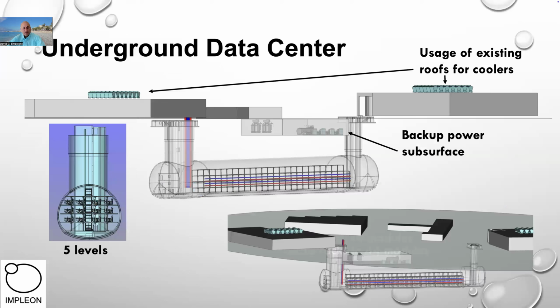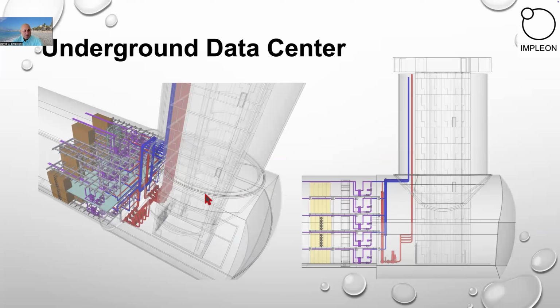And another thing is heat reuse. Usually a data center goes where the land cost is low and the energy cost is low. Afterwards, you start to think about heat reuse and realize that there is no one in the neighborhood, or you need to invest a lot of money in piping to be connected to the district heating grid. From that perspective, we created an underground data center, which allows us to bring 3,250 racks close to the users. We need just a shaft space of 10 by 10 meters, and we don't touch the above-ground buildings, and create this space underground. We have designed a row of racks with on-chip cooling, with door heat exchangers if it is only air cooled, and these subsystems are connected to the facility loop, which provides hot water to the city.